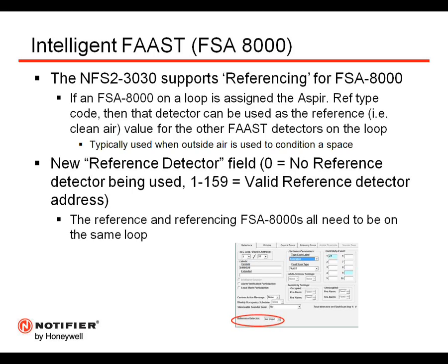So if the reference detector is seeing some contaminant or particulate that's coming in from the outside air, the other detectors that are referencing back to it can see what the clean air value is and determine if they should be going into alarm. If the reference detector is seeing a certain level of obscuration, but one of the other detectors it's referencing is seeing a different and higher condition, that's going to signal that this is a true alarm for that device. The new reference detector field would be zero for no reference detector being used, or it can be set from 1 through 159 for a valid reference detector address. The reference and referencing FSA 8000s all need to be on the same signaling line circuit loop.